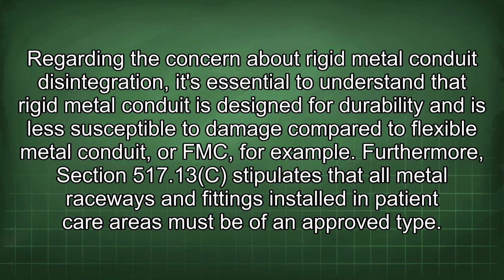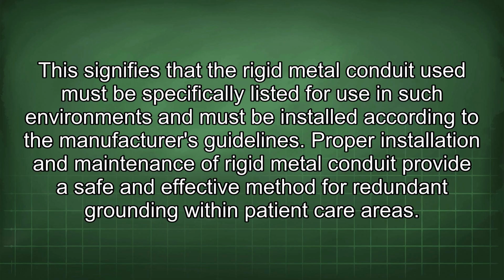Furthermore, Section 517.13c stipulates that all metal raceways and fittings installed in patient care areas must be of an approved type. This signifies that the rigid metal conduit used must be specifically listed for use in such environments and must be installed according to the manufacturer's guidelines.